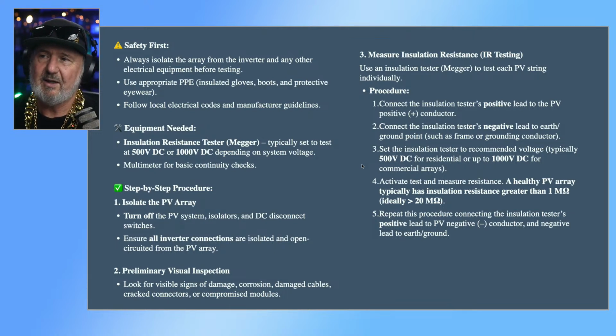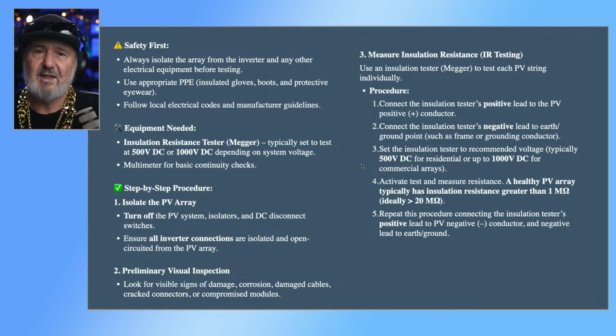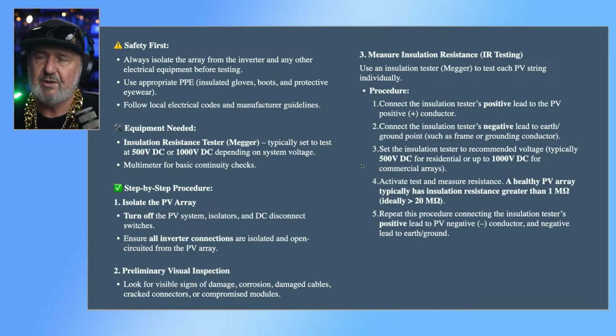So the steps would be: isolate the array, turn off the PV systems isolator and DC disconnection devices. Ensure all inverter connections are isolated and open circuited from the PV array. Then a visual inspection, that's often a good place to start.